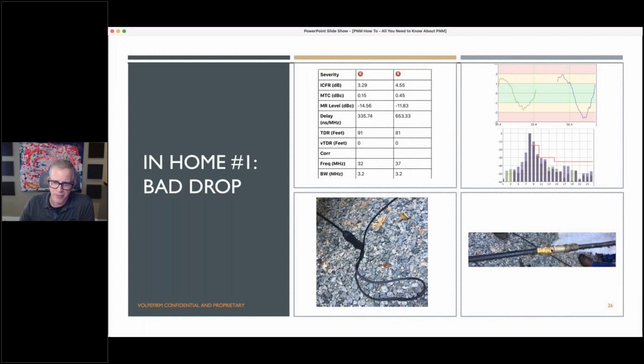When we opened it up though, this was the actual connector that was on there. It had been spliced, but unfortunately it had crimp-on connectors on it. You can see there's some corrosion on this crimp-on connector. Water had eventually infiltrated this splice, and water is that one thing that will just kill connectors, particularly crimp-on connectors.